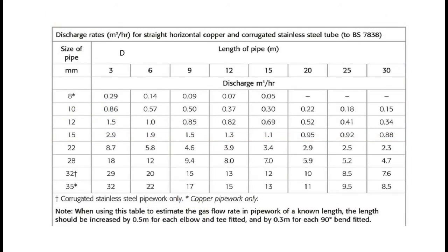Here's the chart. You go across the top. We know that we had 15 meters of pipe. We go down the column to the first number that is bigger than 2.75. In this case, it's 3.4. And all we do then is we go back along, and it shows us the size of pipework that we need to be using. And in this case, it's 22 millimeters.